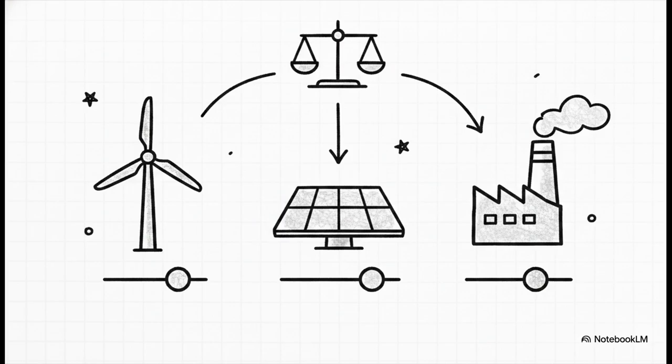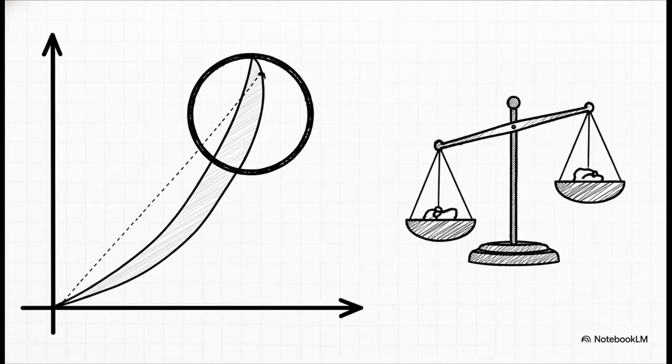We're just telling the units that are already awake to push a little harder or back off a bit, all while keeping our total operating costs as low as humanly possible. To find that rock bottom minimum cost, we've got to look at the math. Every single unit has a total cost curve, which is just what it costs to produce at a certain output level. But the real magic? That happens with the incremental cost.